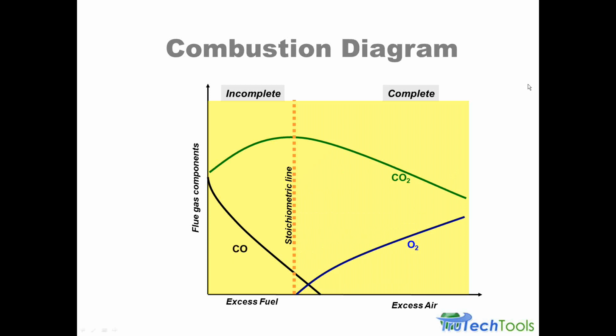This line shows the carbon monoxide. And we do have the carbon monoxide line slipping over into the excess air area because this is more real world. You will get carbon monoxide even though you may have excess air. It's because the excess air is not present in every place and every single location where combustion is happening in the burner system, and air-to-fuel ratios, burning rates and flame stability may be changing to occasionally produce some CO and then again run at perfect combustion. So there usually is some CO produced even though you're beyond the area of perfect combustion. That's just the real world.